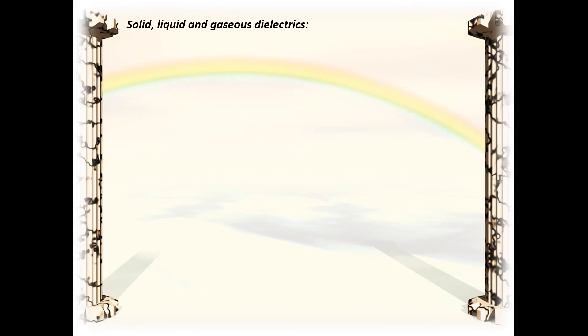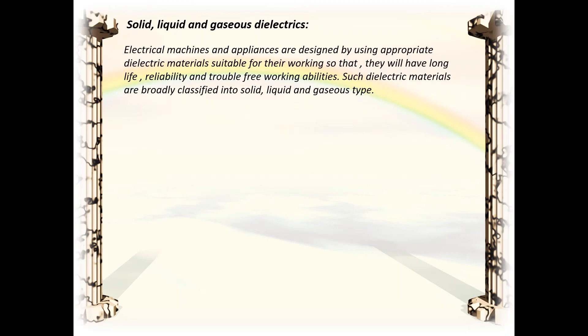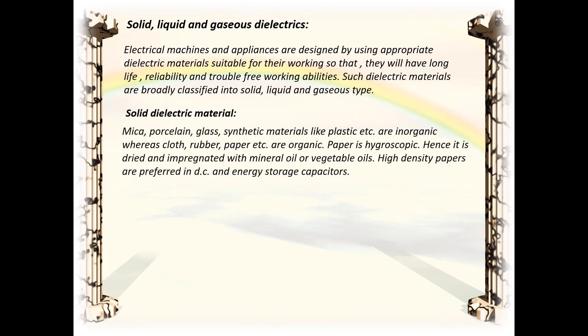Dielectric materials used in electrical machines are broadly classified into solid, liquid, and gaseous types. Solid dielectric materials include inorganic materials such as mica, porcelain, glass, and synthetic materials like plastics, as well as organic materials like rubber and paper. Paper is hygroscopic and hence is dried and impregnated with mineral oil or vegetable oils. High density papers are preferred in DC and energy storage capacitors.